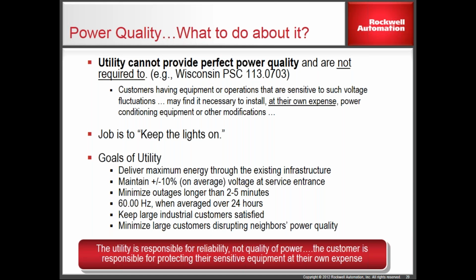Well, here's the reality, guys. The power companies are on the hook for reliability of power. That's their job, to give us reliable power. Sometimes to increase that reliability and deal with the grid the way it's designed, they get that reliability by switching around the problems. You hit a pole, it would have knocked the power out to that plant. They don't want that plant to lose power, so they switch the power around the problem.